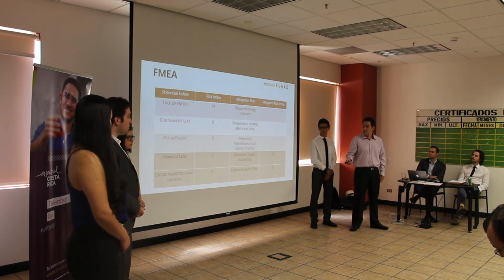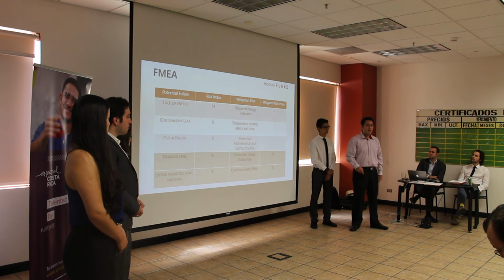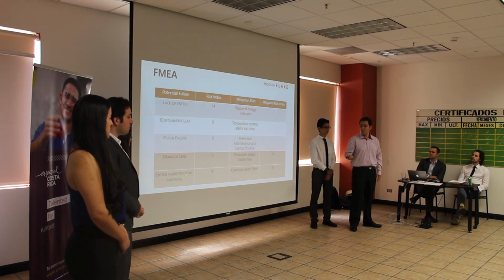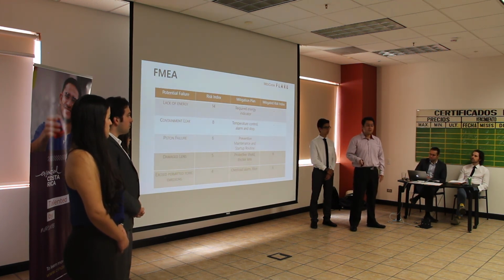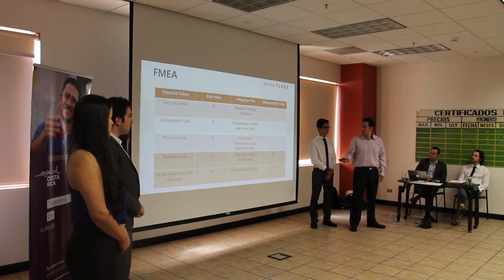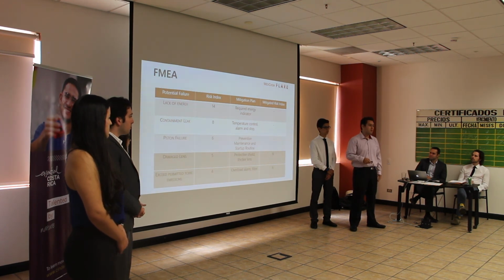And also, exceeding permitted toxic emissions. Our goal for this device is that it's friendly to the environment. So if we are going to do that, we need it to be really controlled. So this is one of our highest risks in this device. We assume that an overload alarm and a filter are going to be a really good mitigation plan for this kind of problem. And with this mitigation plan, the risk index is at a level that we can consider acceptable.